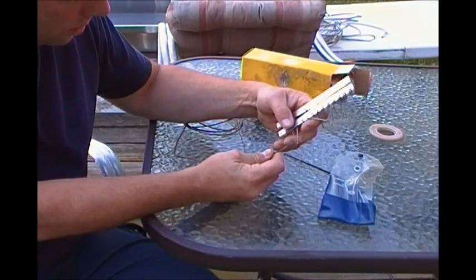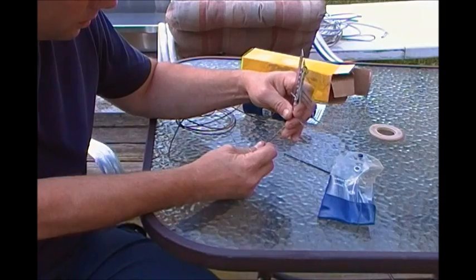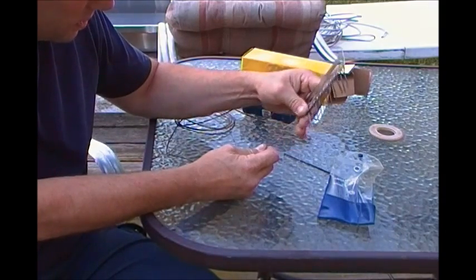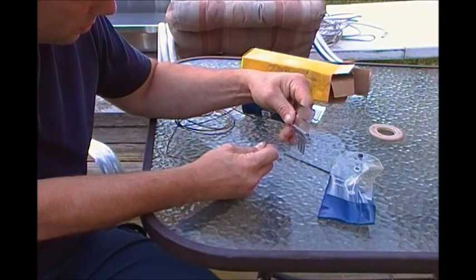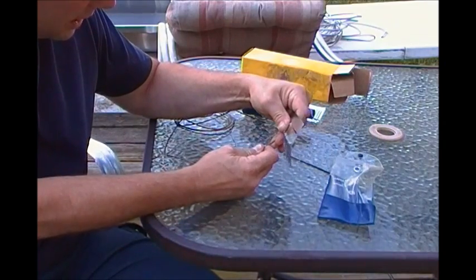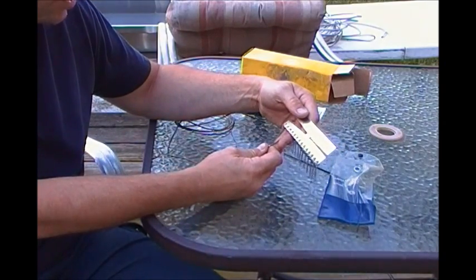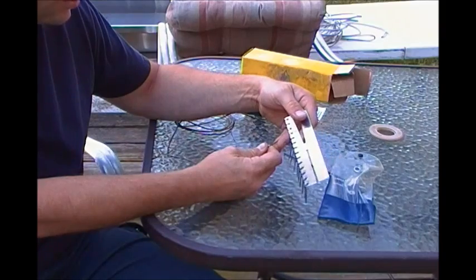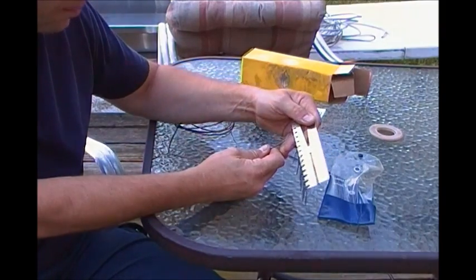So basically we're going to try this one, it fits but it's a little loose. Next one, fits, I think that's it. So it's a .036, that's the inside diameter of this capillary tube.